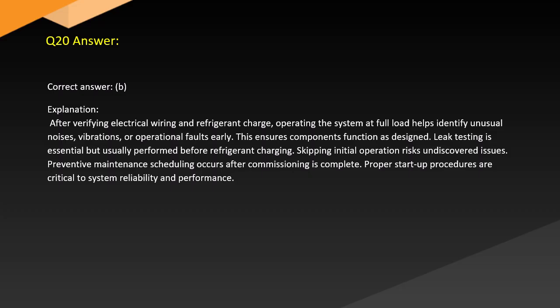faults early. This ensures components function as designed. Leak testing is essential but usually performed before refrigerant charging. Skipping initial operation risks undiscovered issues. Preventive maintenance scheduling occurs after commissioning is complete. Proper startup procedures are critical to system reliability and performance.